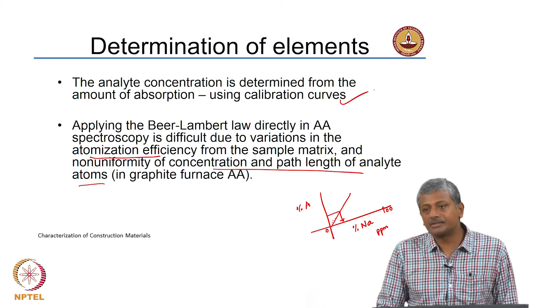So, again, the hollow cathode lamp is the light source; it produces narrow emission in the range of ultraviolet and visible light. A laser can also be used; it produces intensities in the same range of wavelengths. Atomizer: the analyte atoms are going to be sent into the gas phase.